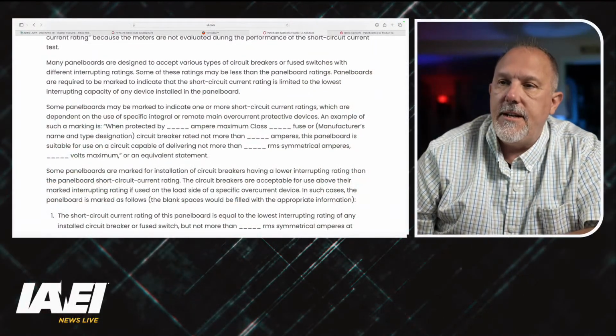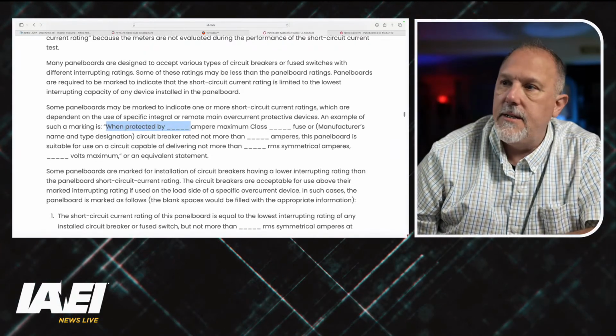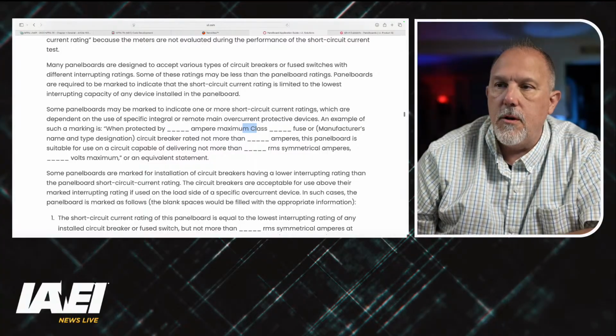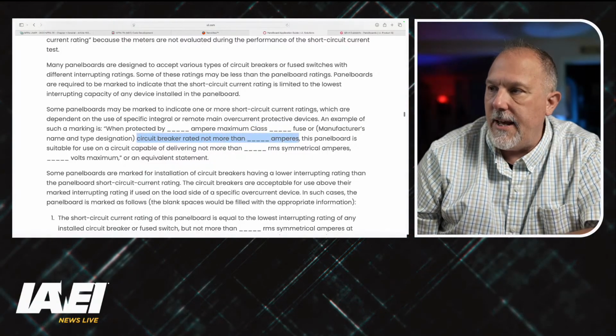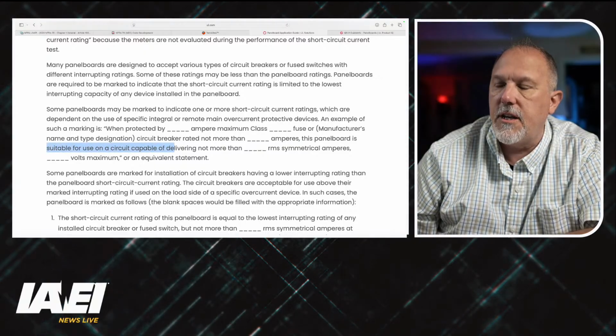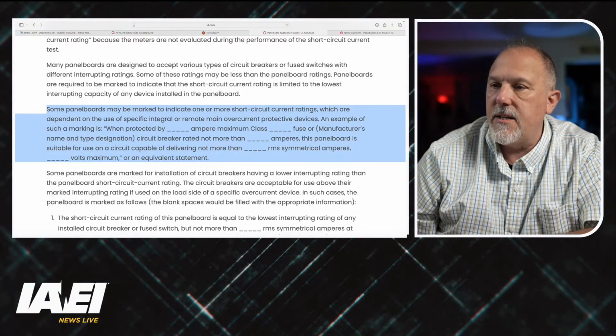But a short circuit current rating, let me see what the UL says. Yes, some panel boards may be marked to indicate one or more short circuit current ratings, which are dependent upon the use of specific integral or remote main overcurrent devices when protected. So here's good language. You see on here where it says when protected by, and they have a spot, ampere maximum class fuse or circuit breaker rated not more than so many amps, this panel board is suitable for use on a circuit capable of delivering not more than blank RMS amps.